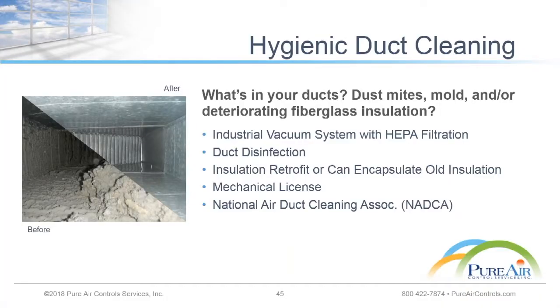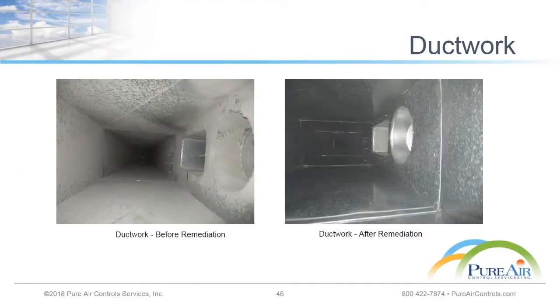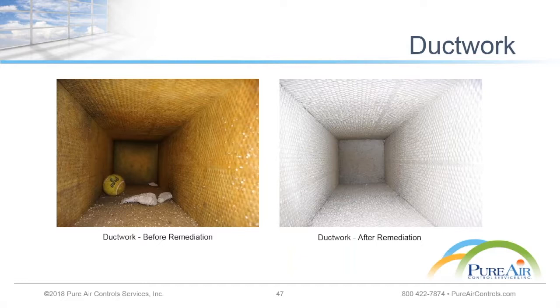Just show them a few before and after pictures, Troy. Yeah, here we go. Just an example there of metal duct on the inside, and then of course there's also a lot of fiberglass insulation duct, so you can see that can also be cleaned. It's a different process - you can't agitate the fiberglass when cleaning fiberglass insulated ducts, so you have to use more of a HEPA vacuum process and compressed air, then encapsulate it with an antimicrobial paint. You can see there, before and after, of a tennis ball from a dormitory.